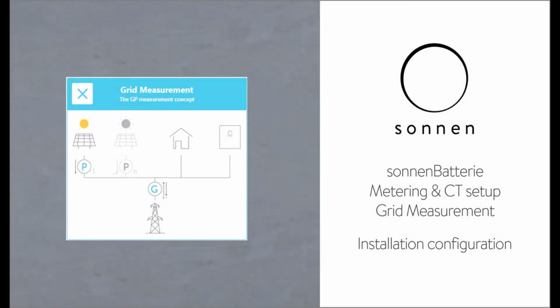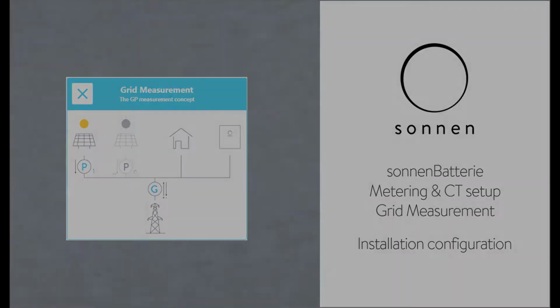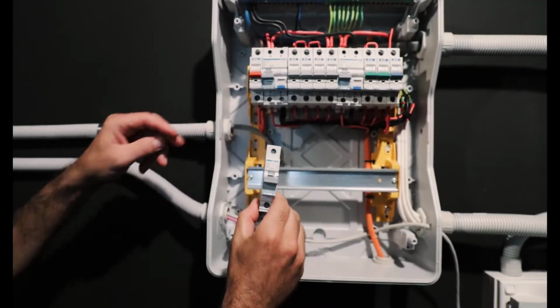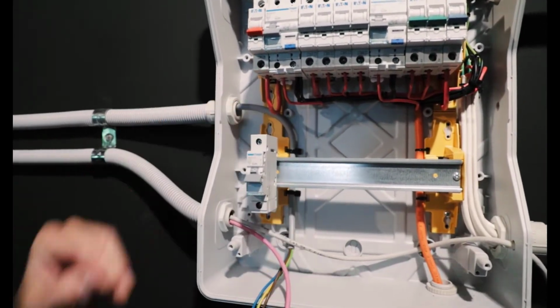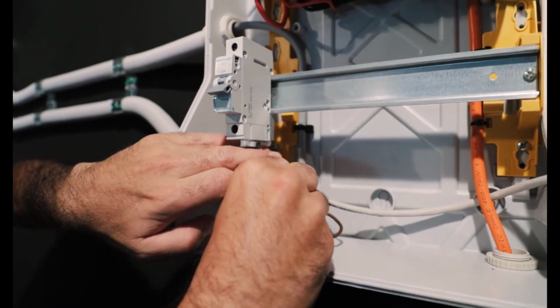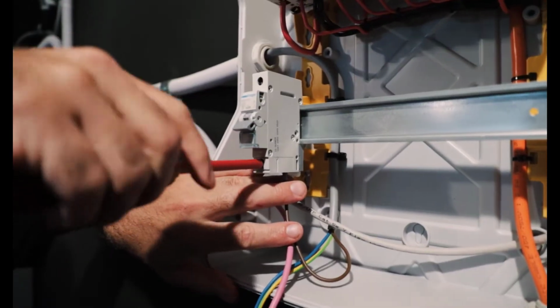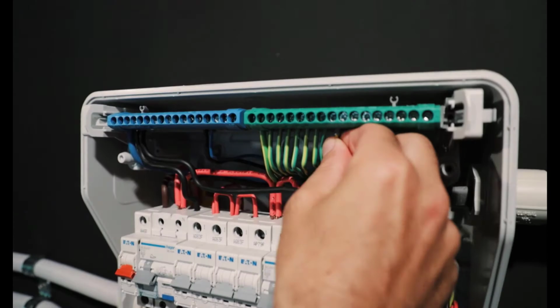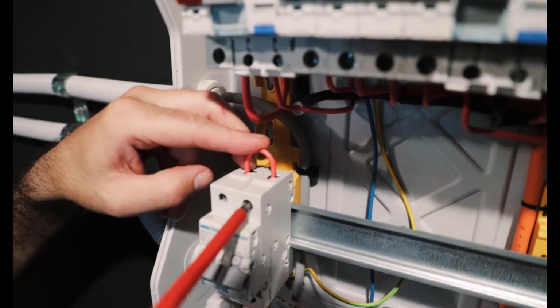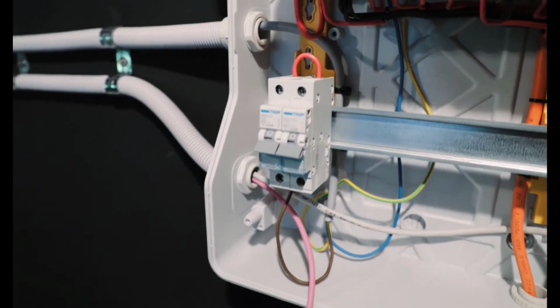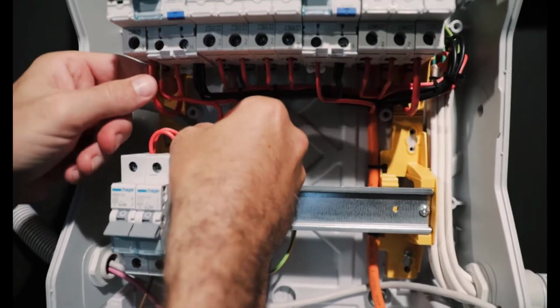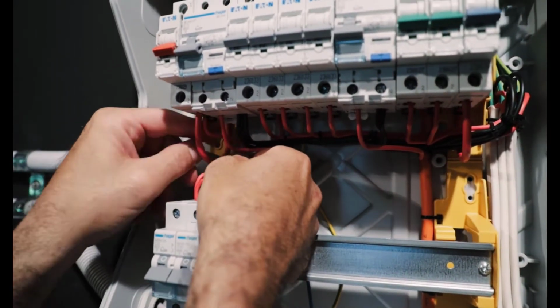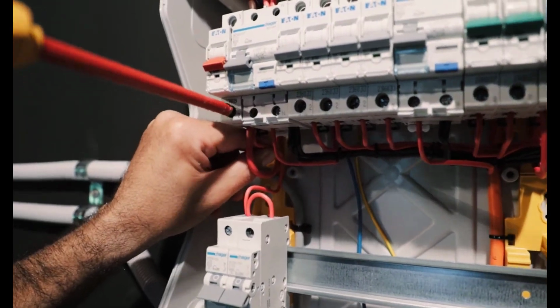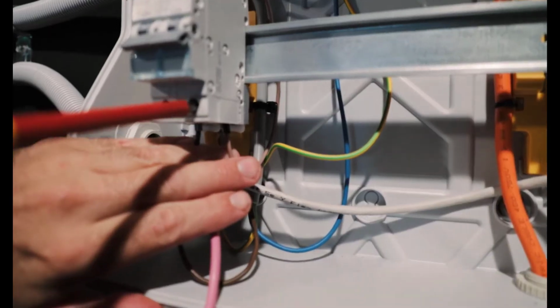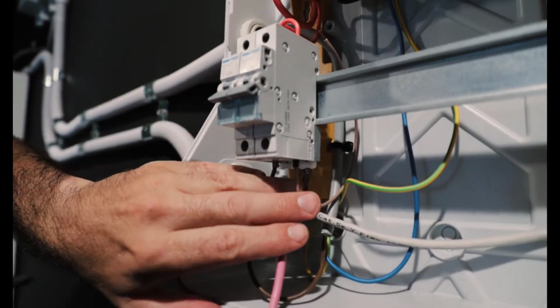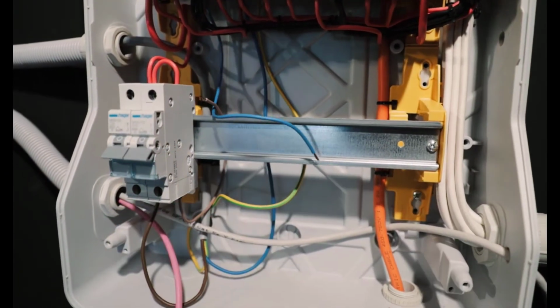So next configuration, again, it's the grid measurement, but grid measurement also taking into consideration any AC coupled PV. So once more, we get the AC connection from the sonnenBatterie system in, earth on and then neutral in. Then we take out MCB for the meter. So the reason we have that MCB is in some circumstances we will want to be able to isolate the meter to be able to restart it, or just to be able to turn it off. And our active supply from the MCB, which will be going to the meter, and neutral coming down.